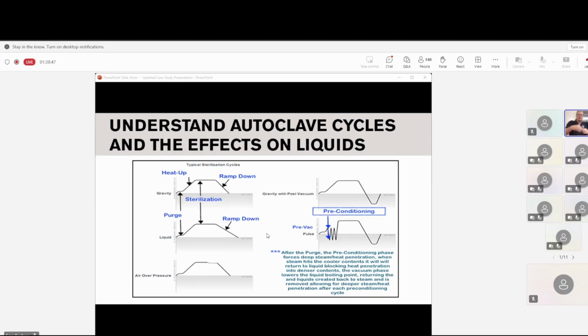So when you get into sterilization, it's going to do the same thing. It's going to run through a hold pattern, and it wants to see if the temperature is going to drop off. If it drops off, then it will pump steam in, and then you get a timeout period. So if it sits there and it keeps going back and forth, it will get a timeout, and that's where you get your heat timeout failure. And when you get a lot of heat timeout failures, it generally is because you've overloaded the autoclave, and the contents are still cold enough that it's causing cool air to go into the drain in the chamber, and it drops down too low, and you get that layer.